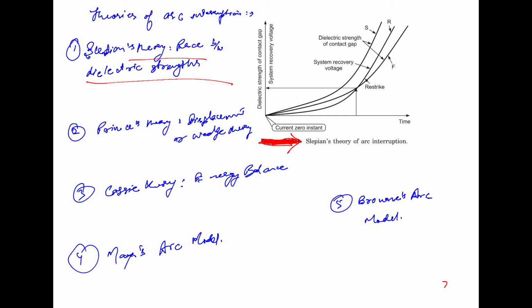Now, Joseph Slepian was one of the early researchers in the field of circuit breakers and has made numerous valuable contributions in this field. According to the theory proposed by him, there is a race between the build-up of dielectric strength of the contact gap and the recovery voltage imposed by the power system. In case the dielectric strength is built up at a rate faster than the recovery voltage, the interruption is successful. Otherwise, the arc restrikes and interruption becomes unsuccessful.